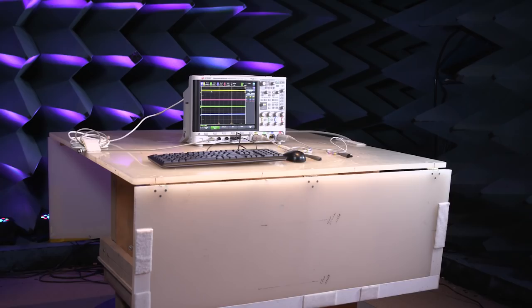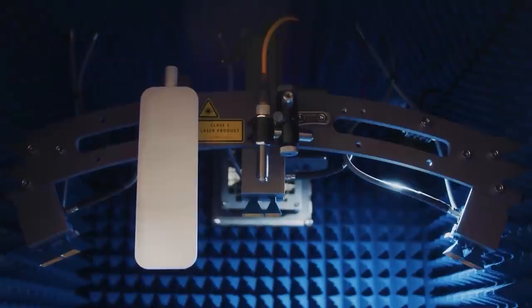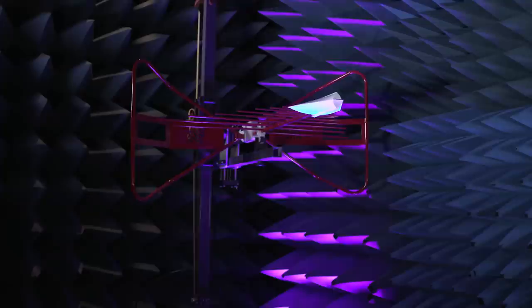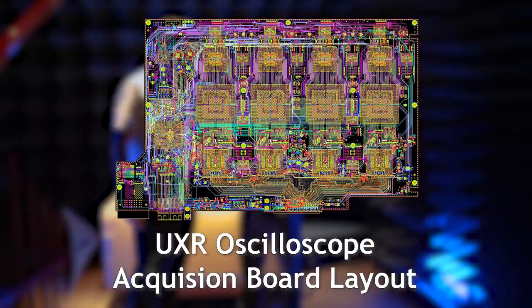These rooms are required for testing audio output levels and electromagnetic emissions. There are stringent government requirements that all products have to meet before they can be sold, and on this team we have safety engineers that can do their own testing and submit the test data to the CSA group and UL for certification — we don't need a third-party lab for that. R&D engineers come down here frequently for gut checks. We're very fortunate to have a PhD who is very involved with R&D — even in the prototype stages he is looking at printed circuit boards for shielding and ensuring that high-frequency traces are shielded correctly, giving good suggestions back to R&D.